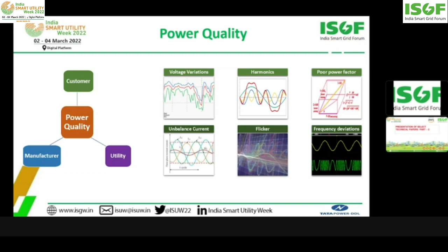Conventional power factor. Fourth is current unbalance, which is the different magnitude of current in all three phases. Then fifth parameter is flicker. Flicker is a sensing light fluctuation which can cause irritation to human eyes and brain. Then frequency deviations. It is a deviation from standard supply frequency for India, which is 50 hertz.